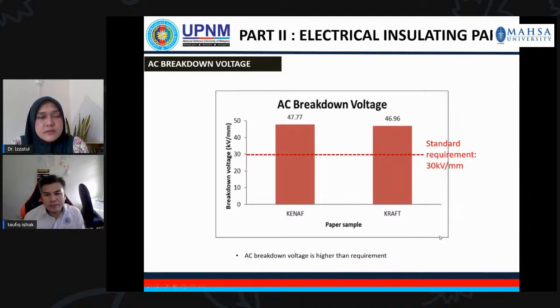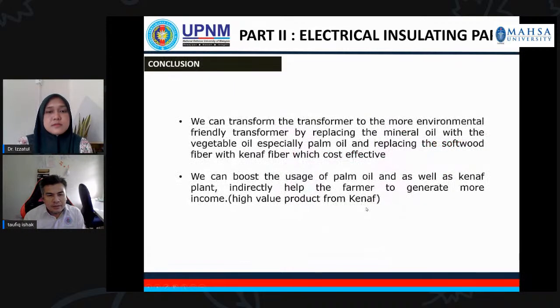And then in terms of AC breakdown voltage, the standard requirement, similar to the liquid, is 30 kV per mm. And then both Kenaf and Kraft paper perform beyond the requirement by the standard, which is 47.7 and 46.96, which is almost equal in terms of performance. So the conclusion that I can make from the initial study of the electrical insulation paper, we did some study, yet it is still an ongoing study in this area.